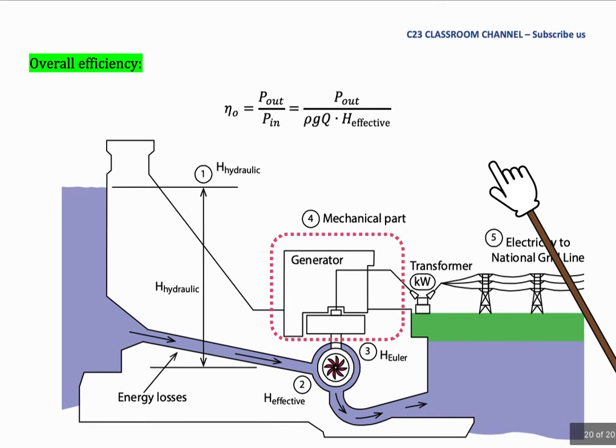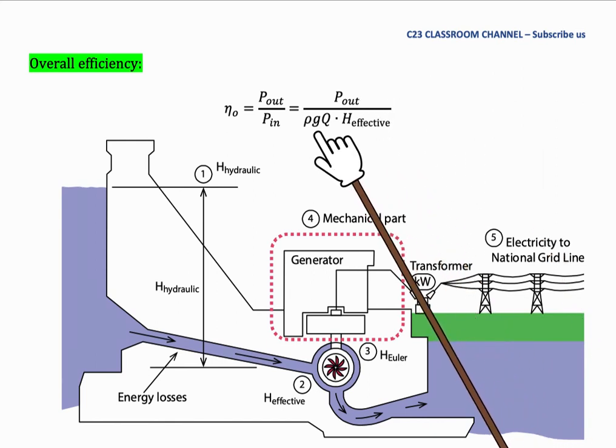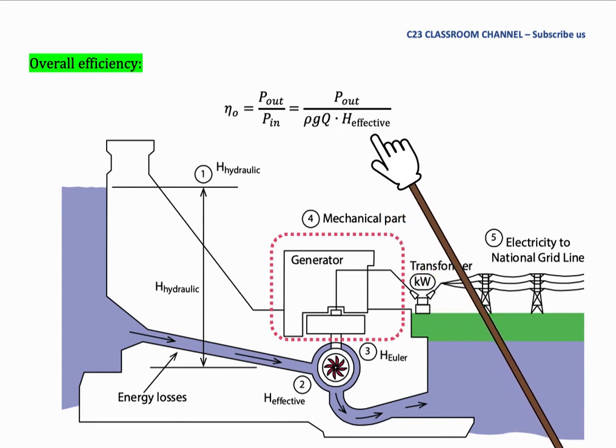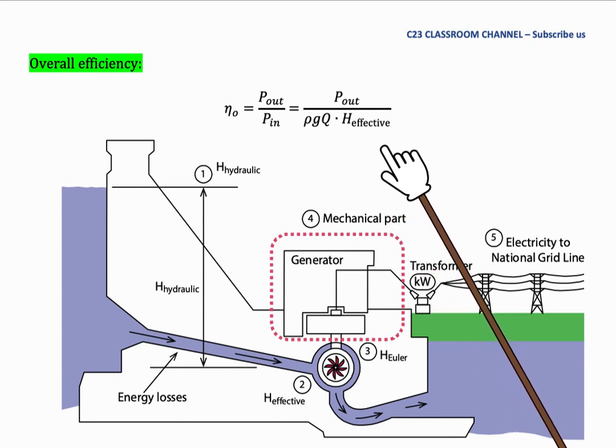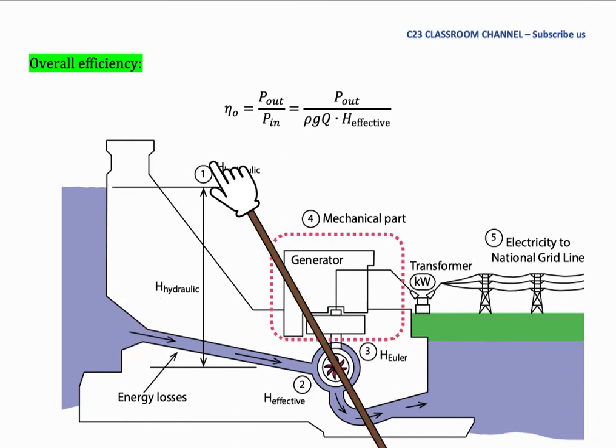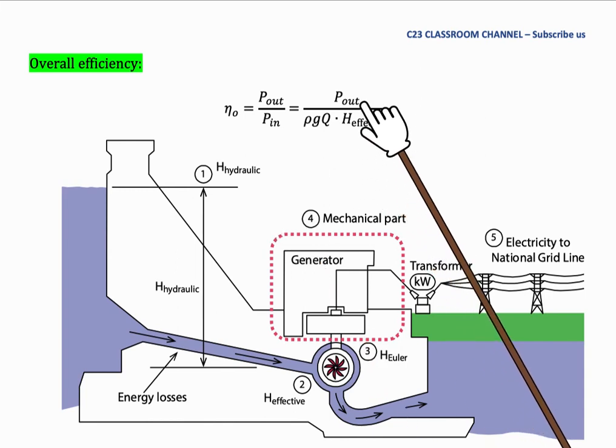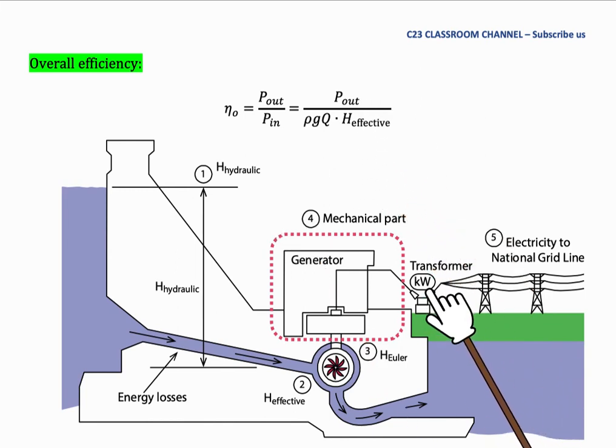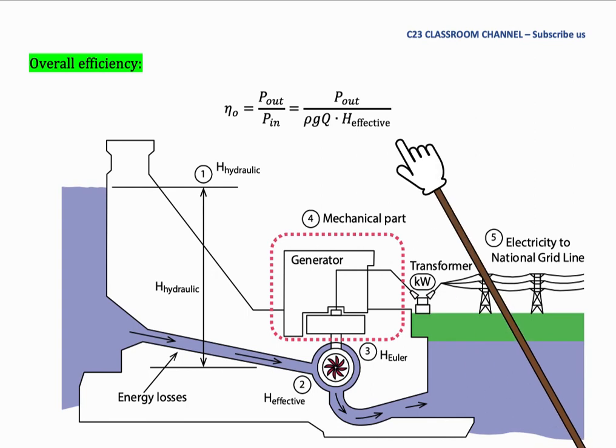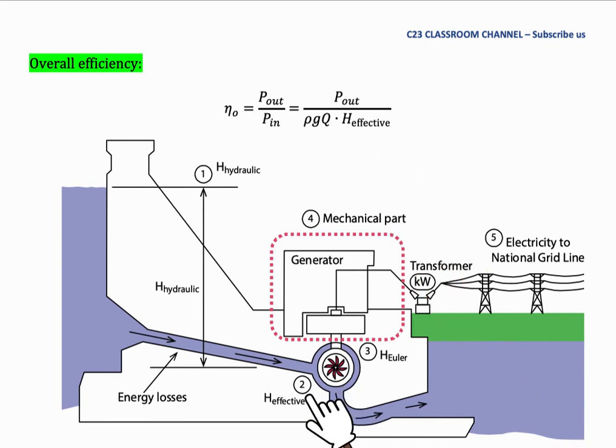Overall efficiency can be defined as power out divided by ρGQ·H_effective. Overall efficiency is the efficiency of the overall system of the Francis turbine. The power out is the power that we could get at the transformer, and the input power is from H_effective.